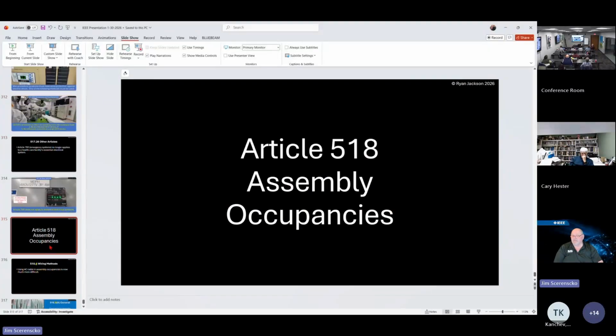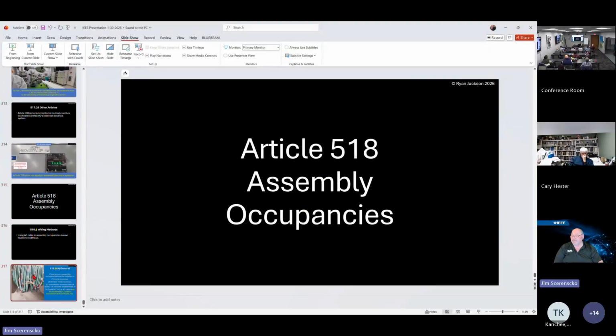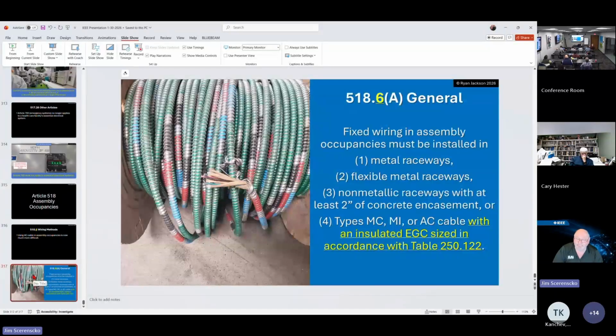There was a change in assembly occupancies too about using AC cable, ACMC, and all has to have an insulated equipment ground now, which AC cable does not have. So you must have an insulated equipment ground in an assembly occupancy.